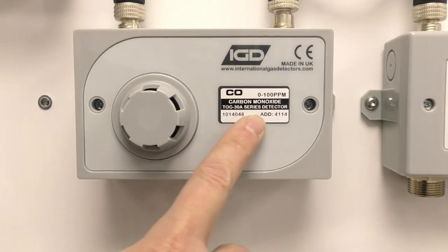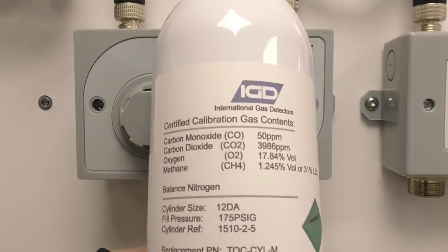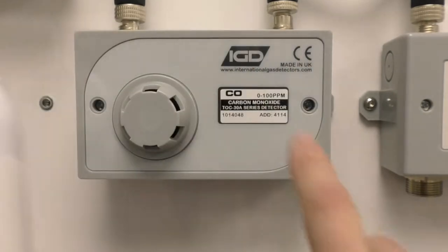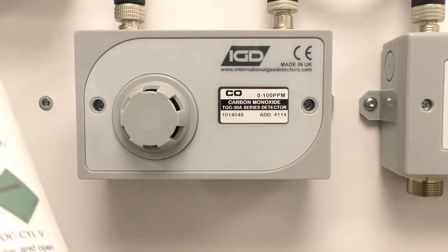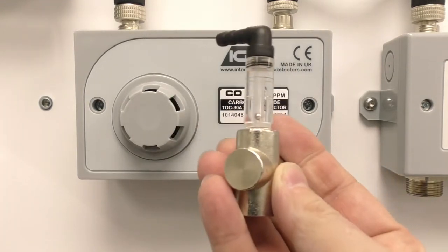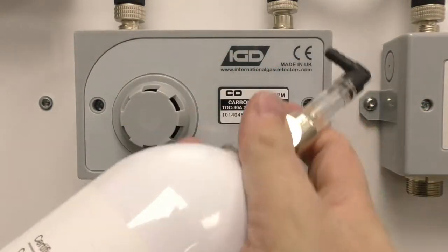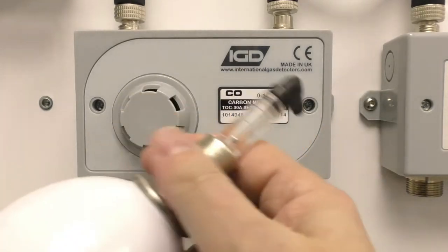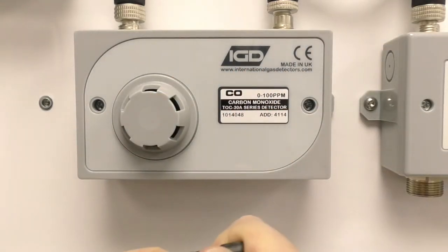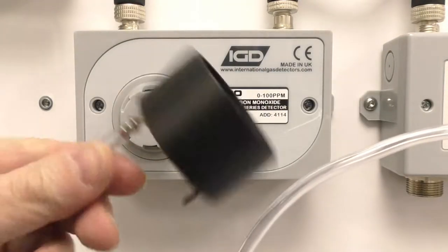Here we are with a CO detector that we've decided we're going to bump test. Here's our calibration gas bottle from the kit — our bump test gas. We can see from this we've got carbon monoxide in this bottle at 50 ppm, so we can use this to bump test this 100 ppm range detector. The cal kit comes with a flow regulator. We're going to screw that onto the top of the bottle, making sure the valve's closed at this point. There we go, we've connected up. We're going to put our tubing on, and I've got my cal adapter all tubed up.